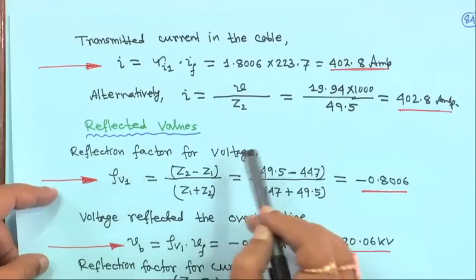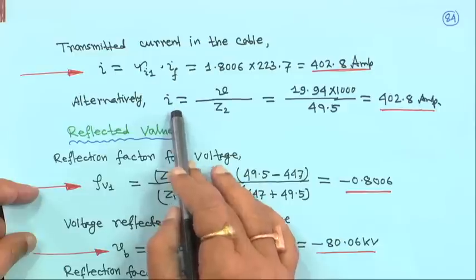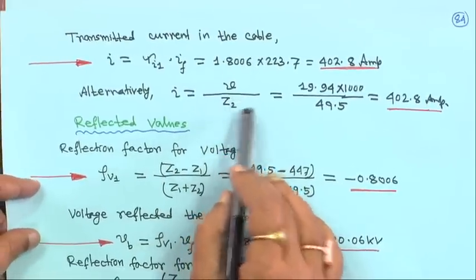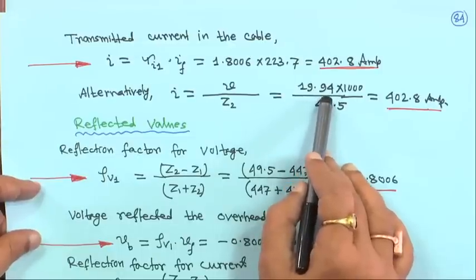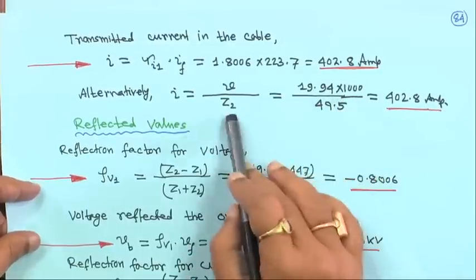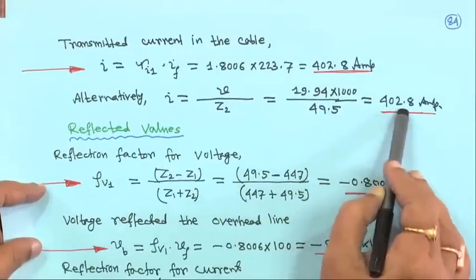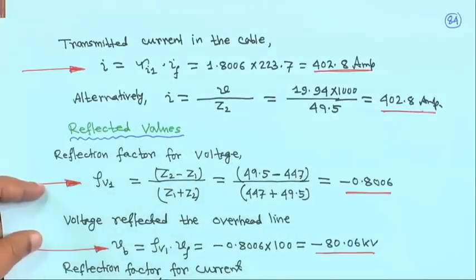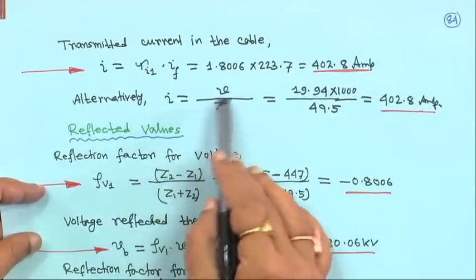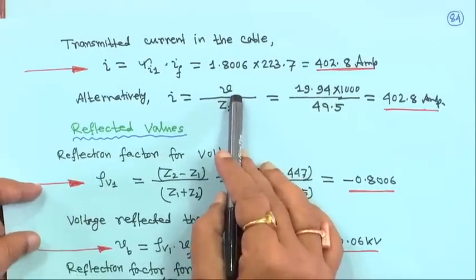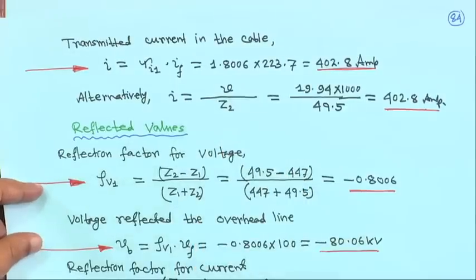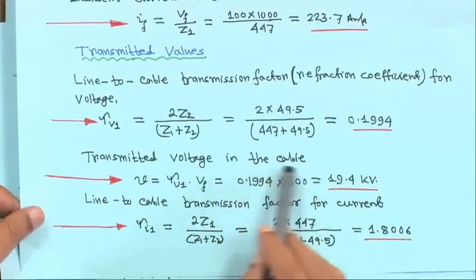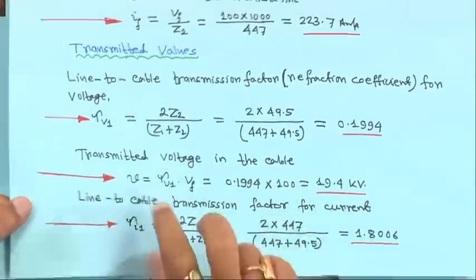Alternatively, for checking: current I equals V upon Z2. The refracted voltage is 19.94 kV, so dividing 19,940 by 49.5 gives 402.8 amperes — the same result. Both methods give identical answers for the transmitted current.